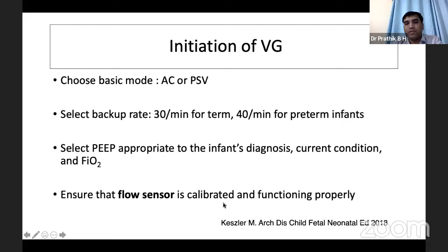The next step is to select the positive end expiratory pressure, PEEP, which is appropriate to the infant's diagnosis and clinical condition, and also to set the FiO2. And the most important thing in initiating volume guarantee, that is tidal volume targeted ventilation, is to ensure that the flow sensor is calibrated and properly functioning. Without a proper flow sensor, you can't give volume guarantee. Once you've done all this, the next step is to select the targeted tidal volume. The tidal volume target depends on the disease condition.